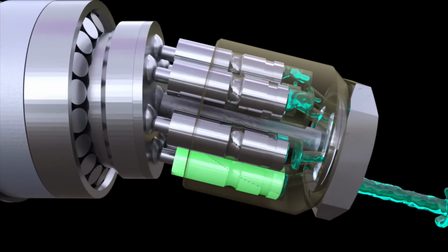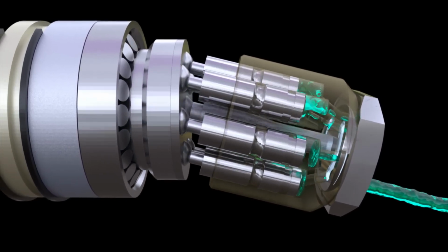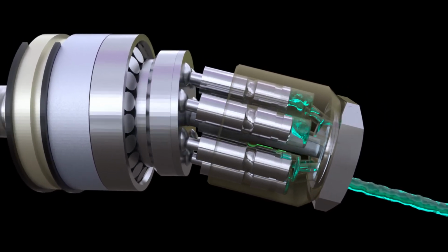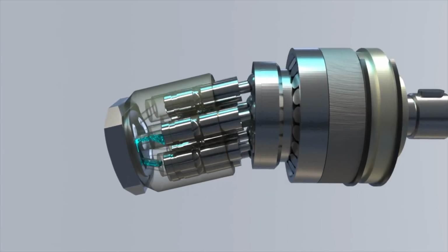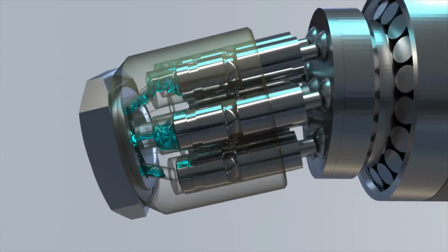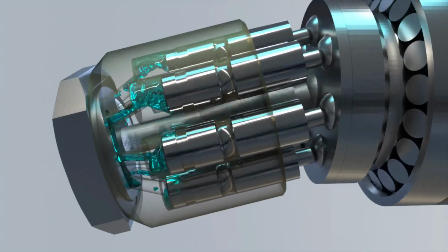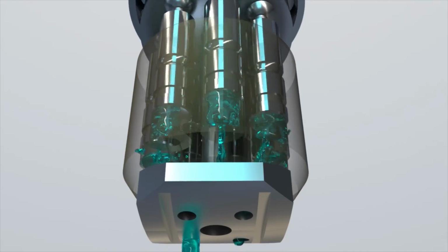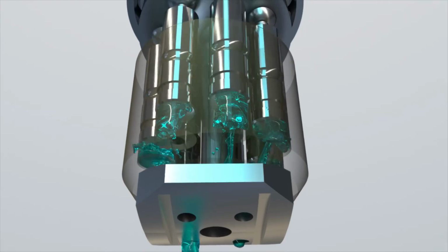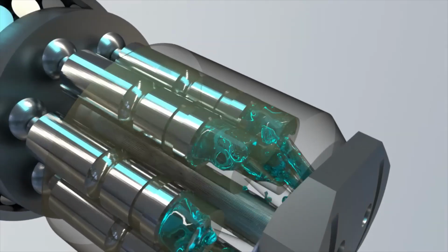Having reached the second extreme position, the piston begins to increase the volume of the chamber again. The suction begins, and the cycle repeats. Several pistons are installed in the pump housing. There are 7 in the example provided. While one piston performs suction, the other is pushing the fluid into the pressure line, and the third is in the extreme position. This design allows for a continuous supply of fluid with relatively low pulsations.